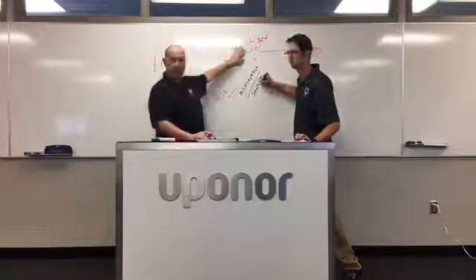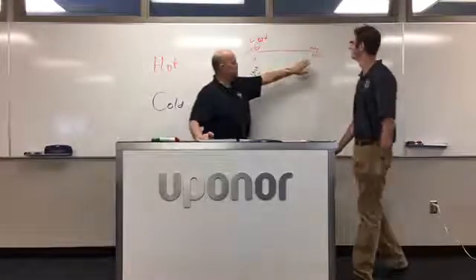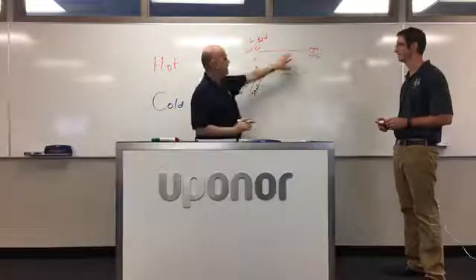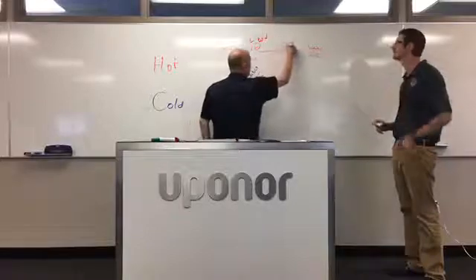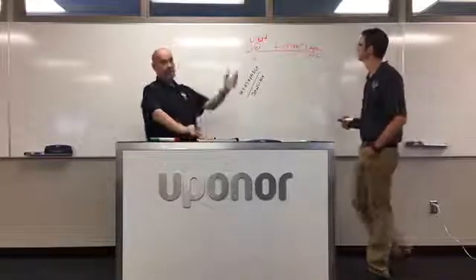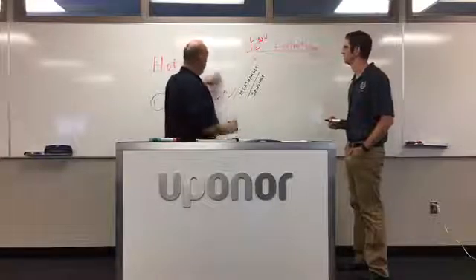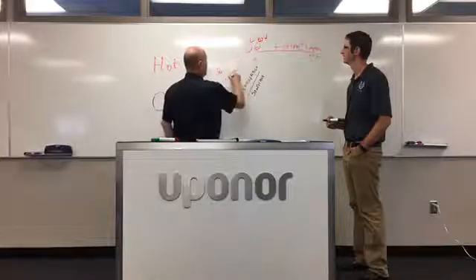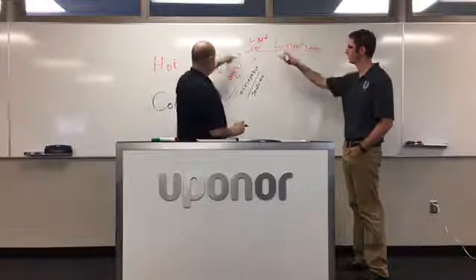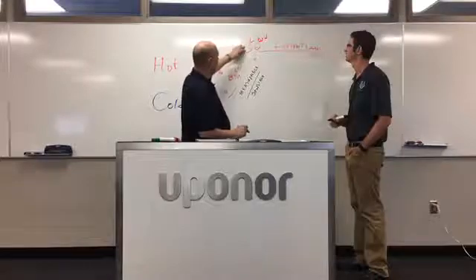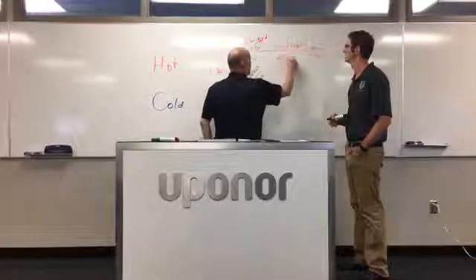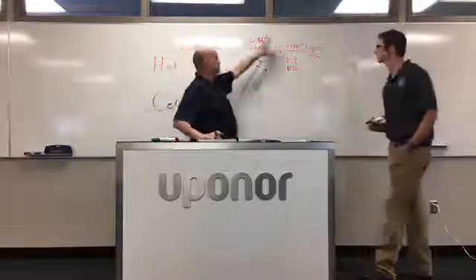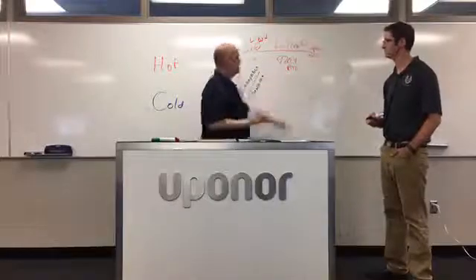At 212 degrees you have liquid water, and at 212 degrees you also have vapor — the same temperature but the heat is hidden in the vapor, so we call that latent heat, from the Latin word for 'hidden.' It takes 180 BTU to raise one pound of water from 32 to 212 degrees — one BTU per degree — but to move that same pound of water from liquid to vapor takes 970.4 BTU just to change state.